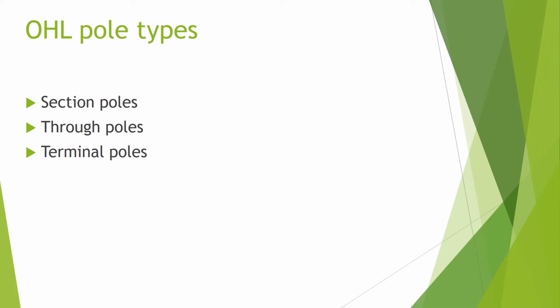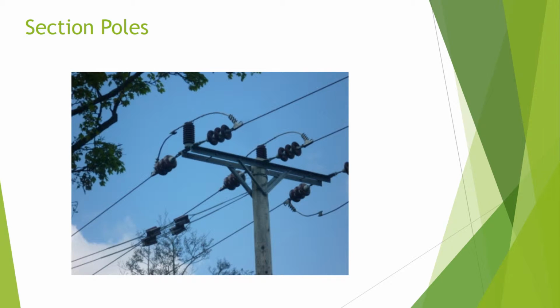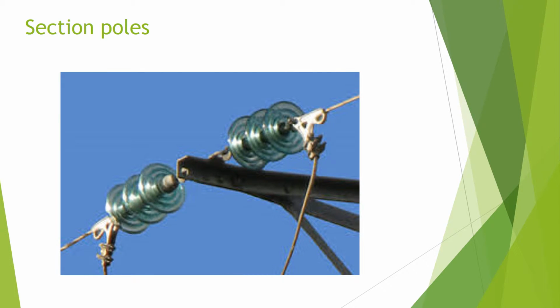Overhead line poles can usually be described as one of the following three types: section poles, through poles, or terminal poles. Section poles are normally found wherever the line has to change direction. Two sets of dish insulators, known as strain insulators, are mounted either side of the crossarm, and to these the line conductors will be terminated and tensioned.